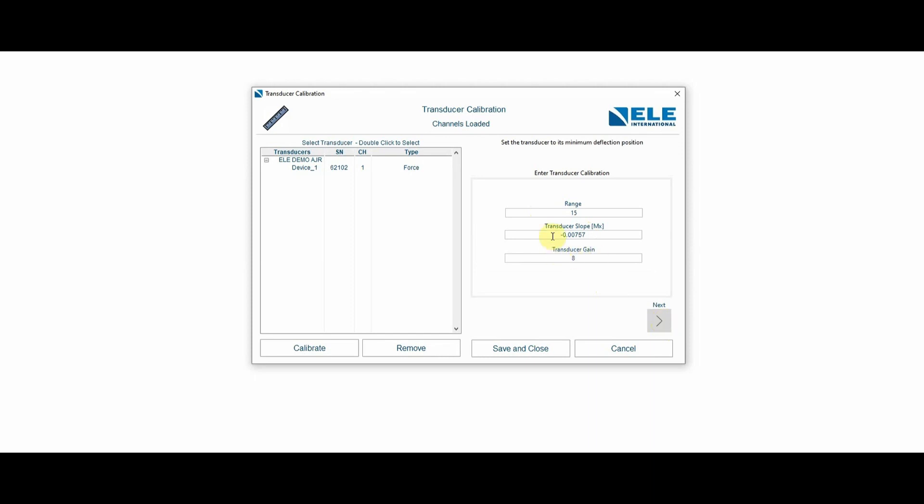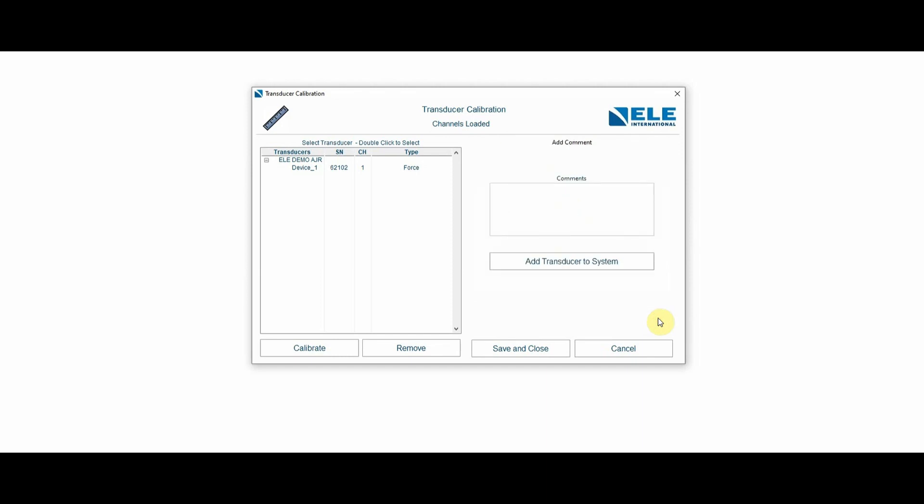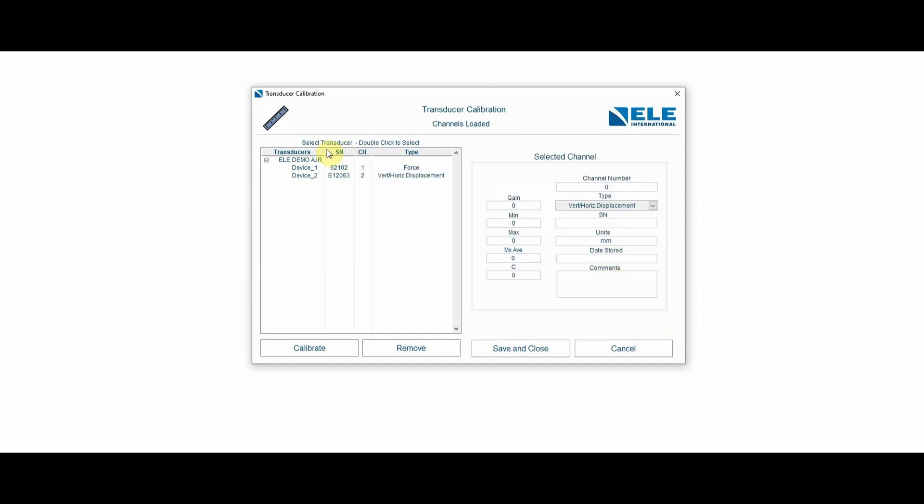Notice that the transducer slope, I've entered with a negative value. You may need to change this after you monitor the transducers, depending on the readings that you get from it. But for now, I'm just entering the data as it's shown up, and I'm going to add that transducer to the system.